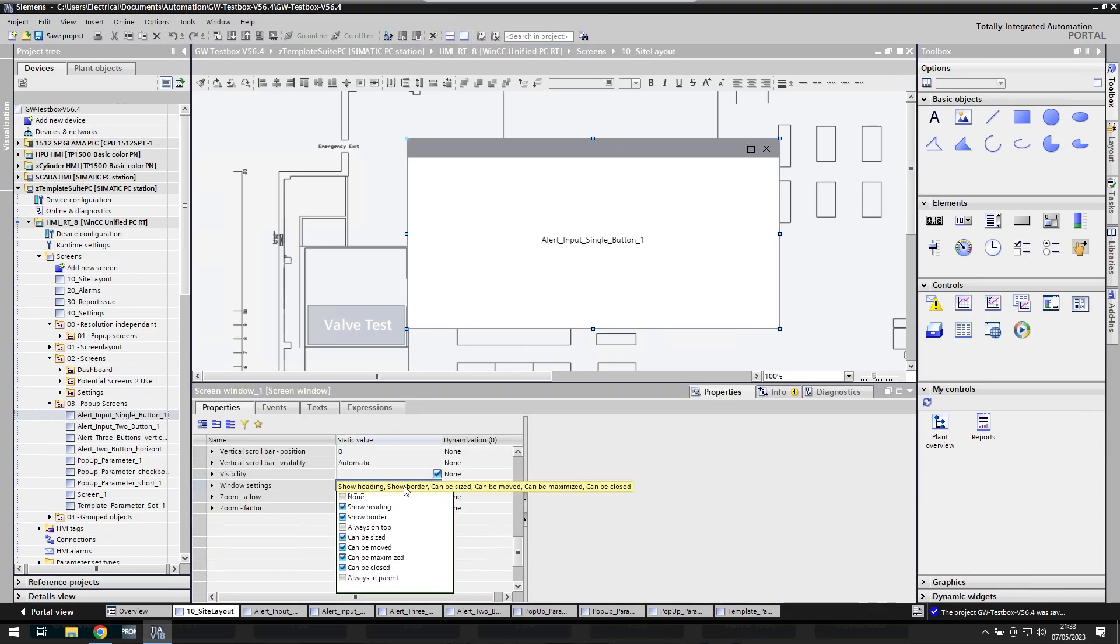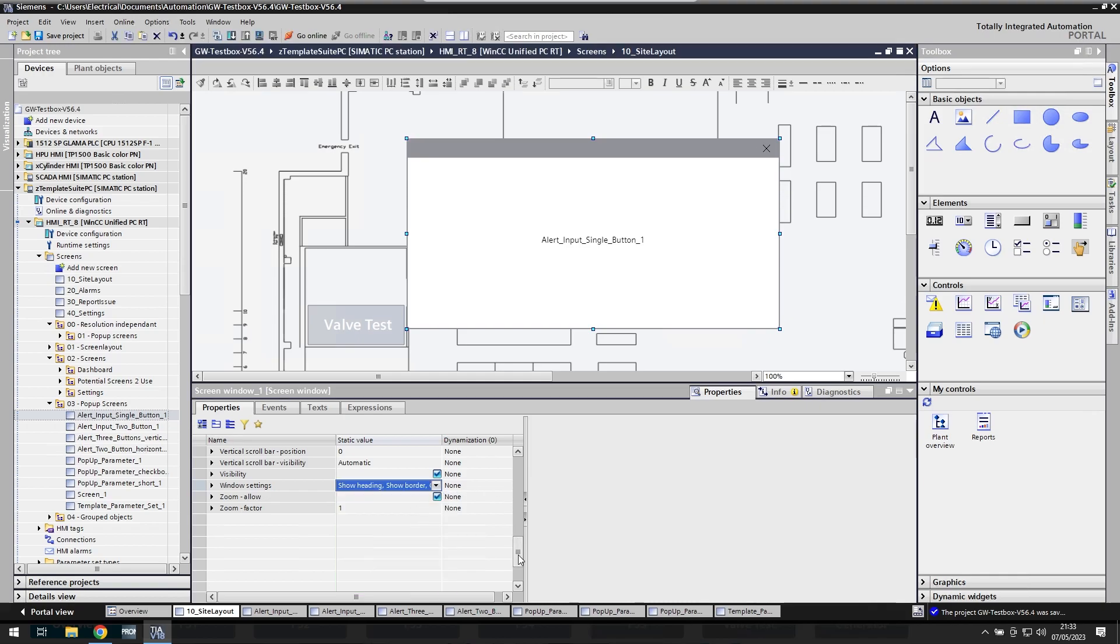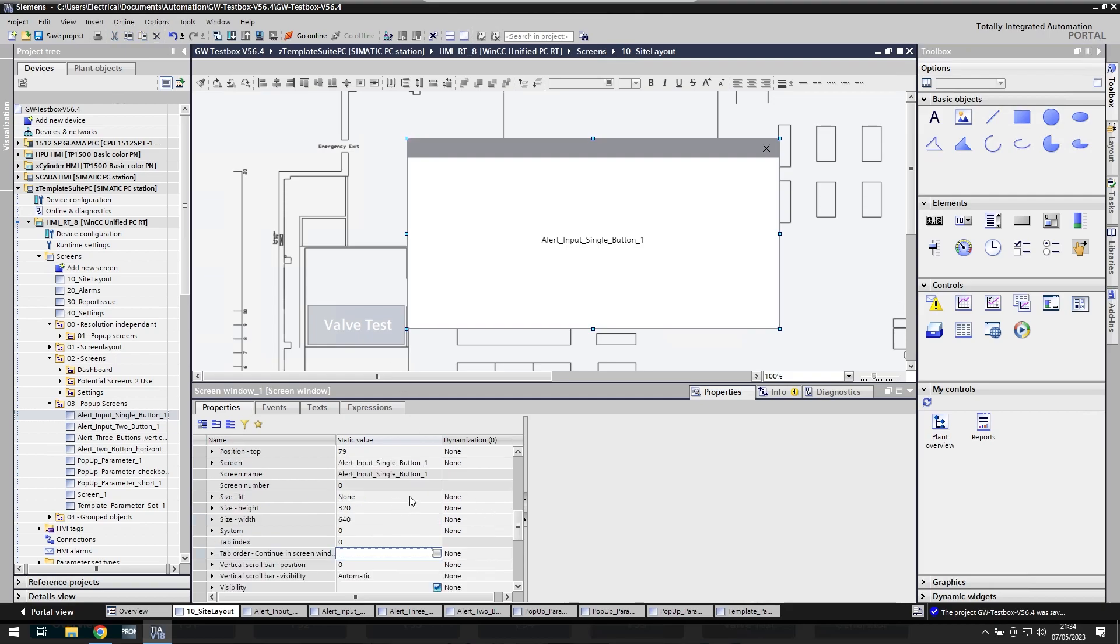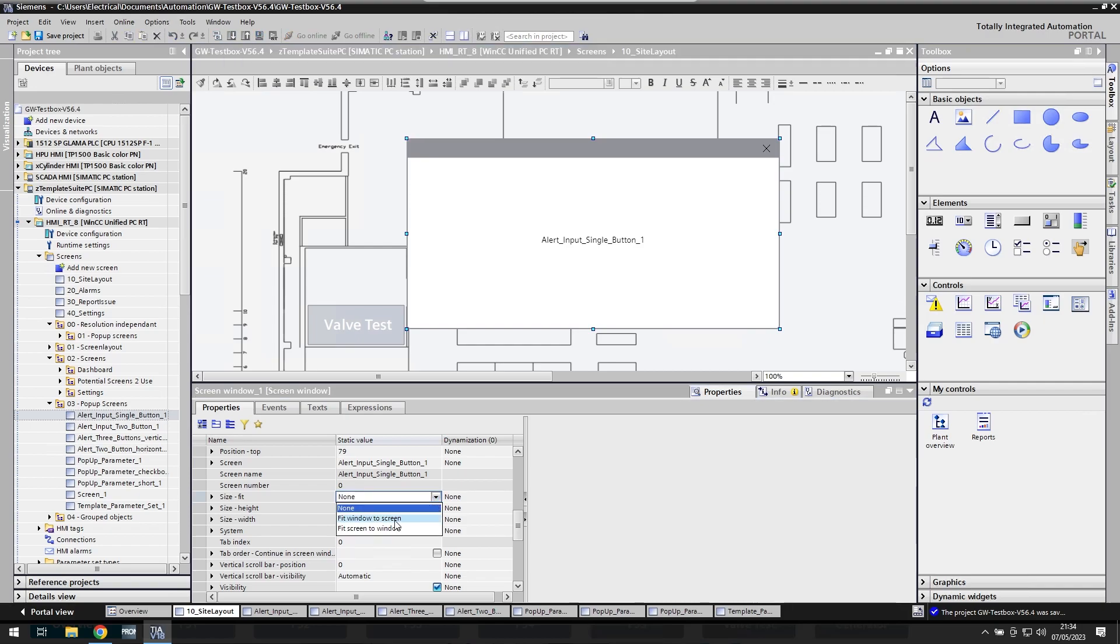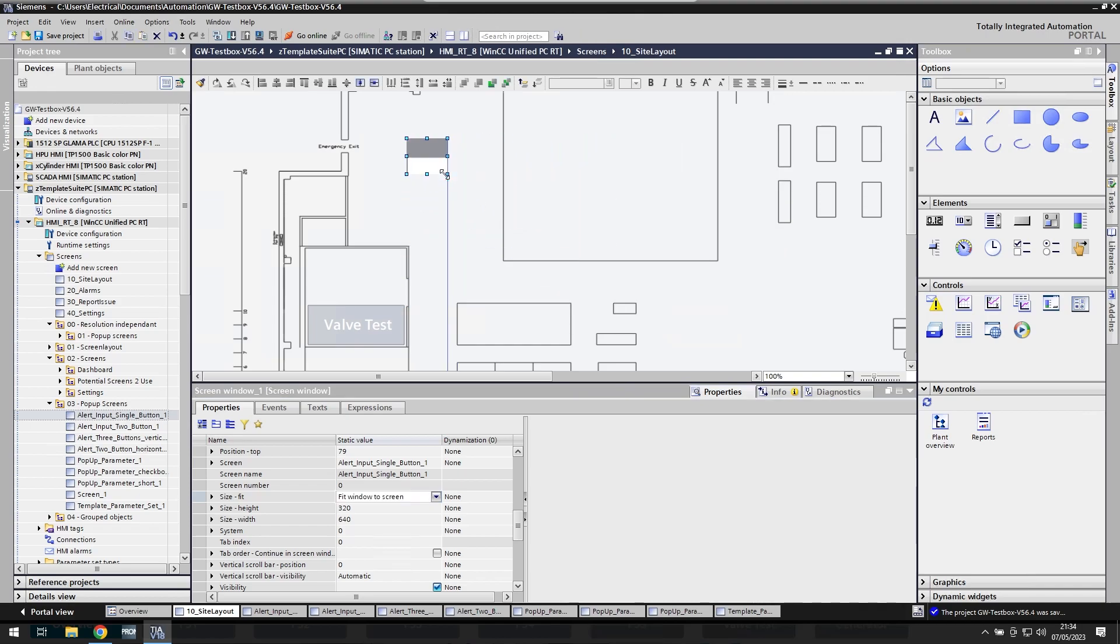So it should be as simple as going to toolbox and then doing a screen window. I think the important point is when the screen pops up, I want it to be close, I want the screen to be closable. I don't necessarily want it to be, I don't want it to be maximizable. Do I want it to be moved? Maybe. Do I want it to be sized? No. The show header, show border can be moved and it can be closed. And then I also want the visibility. I'm going to add that onto the click. I want the window to match the size of the screen. I don't want to set it. So, okay. So size fit and then here fit window to screen. Yeah. So IE change the size of the window to fit the size of the screen. So if I just do now, I can do this. I think if I download to that, it should just automatically become the same size of that screen. Refresh.